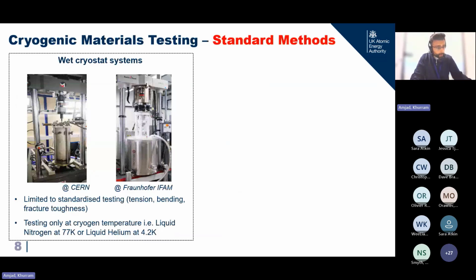Okay, before I jump into our rigs, I'd like to provide a brief overview of the standard methods for testing. Historically, when we talk about low temperature testing, we talk about liquid filled dewars which are fitted onto the load trains. And in these traditional setups, the testing is limited to cryogen temperature. So for nitrogen, 77 Kelvin, and for liquid helium, it's 4.2 Kelvin. And if we somehow do it for liquid hydrogen, that would be at 20 Kelvin.